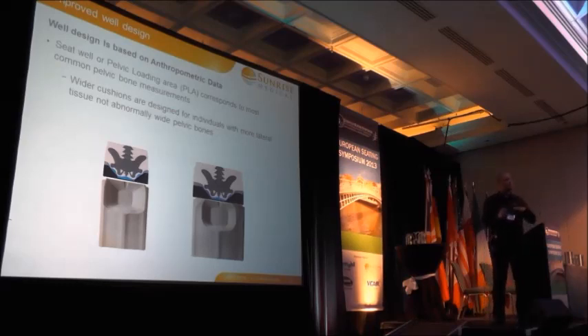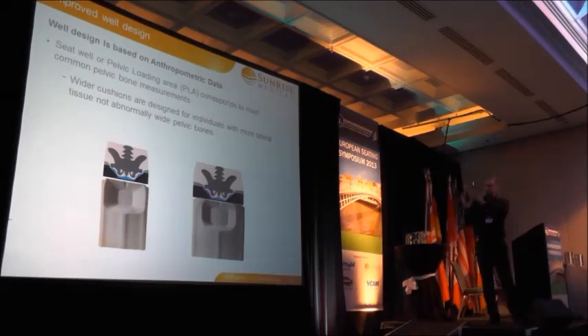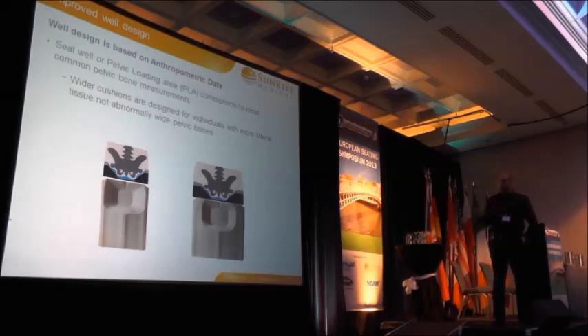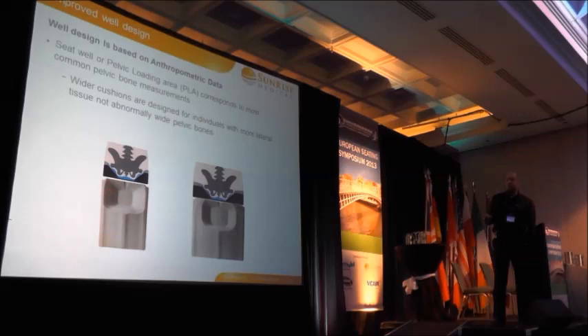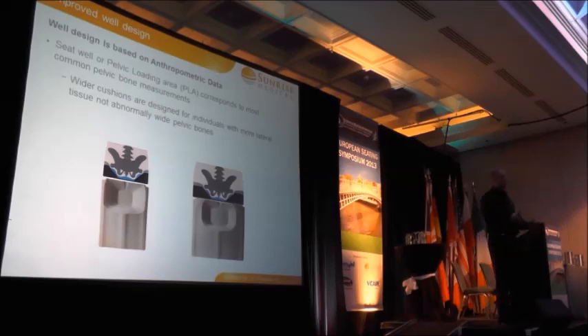What that enabled us to develop when we looked at the J3 was the concept of the pelvic loading area. Now, with wider cushions, as you increase the width of a cushion you're increasing the lateral surface here. The well size is predetermined to support the greater trochanters and allow immersion and envelopment for the ASIS. For the smaller hip width, we have a smaller well size, still going through the greater trochanters. When you increase the width of a cushion, you're increasing the lateral tissue. Looking at bariatric users — 20 inches wide — they will have the same pelvic loading area as a person that's 24 inches wide.